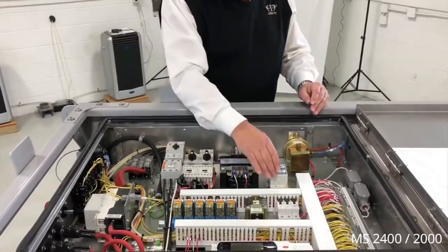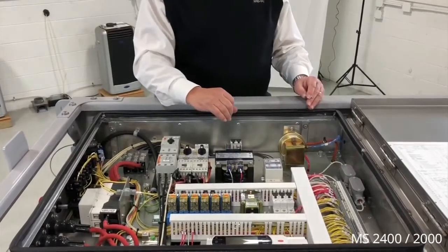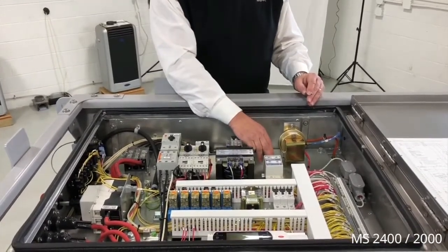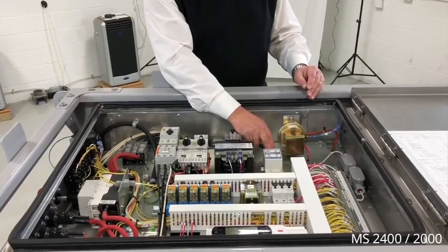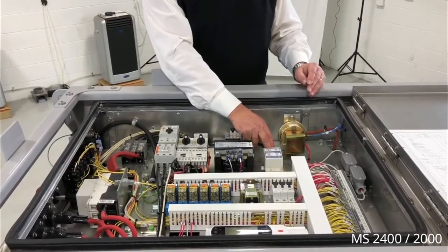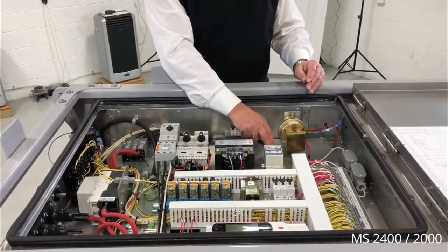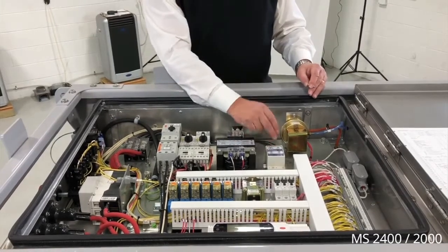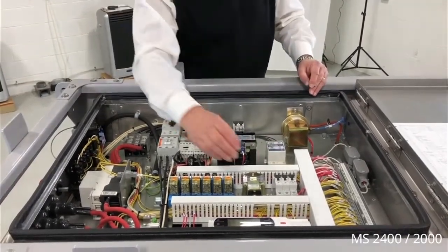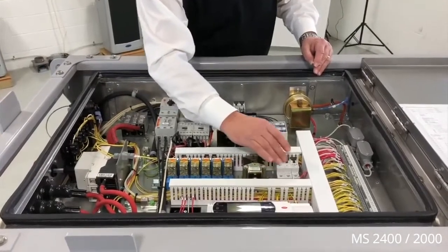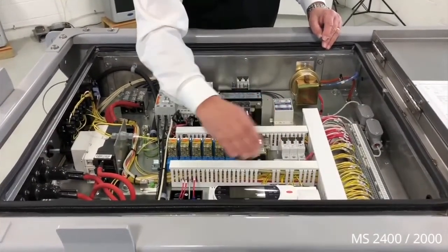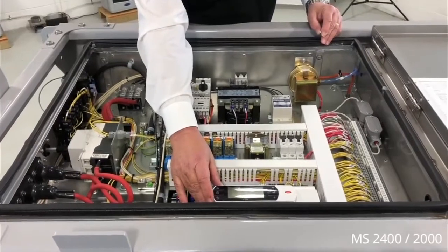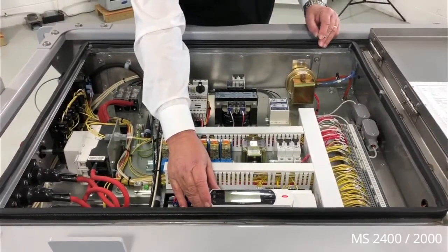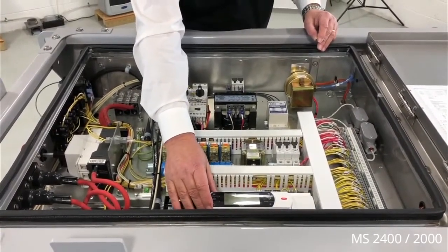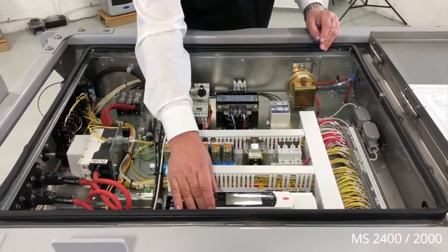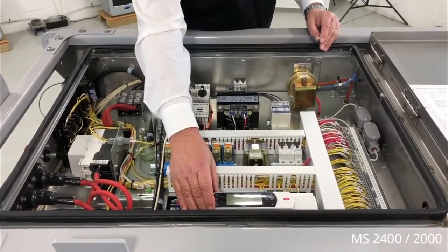Control transformer. This is a phase monitor and voltage monitor to monitor the phase of the electric power coming in and the voltage. If either one of those is incorrect, it will prevent the unit from operating and it will light a fault light. Here are some more circuit breakers for the control part of the unit. And this is the brains of the unit, the little Carel controller that controls the reactivation heat capacity, the blower staging, and then monitors all the phases of operation.